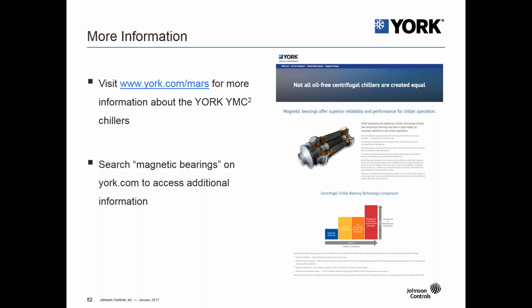Yeah, we did just get a question, specifically asking if a heat recovery can be added to a YMC² chiller. Yeah, so we do have a heat pump option, so it would still be a single circuit or single water circuit on the condenser side, not a dual circuit with multiple connections. But you could still use the condenser for heat reclaim or for preheat through the system.